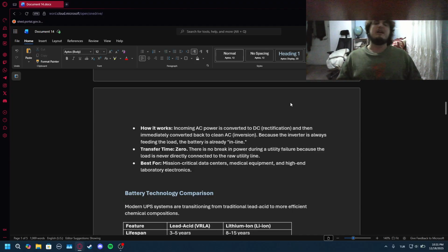So it basically means that I get the AC, and regardless of the irregularities in the voltage, I am just going to turn this into DC, then to the AC that I would be using. And it will be clean because I'm doing two transitions back to the power I need. So this way, it can actually feed the network and be, let's say, more efficient and make the harmonics disappear, basically.